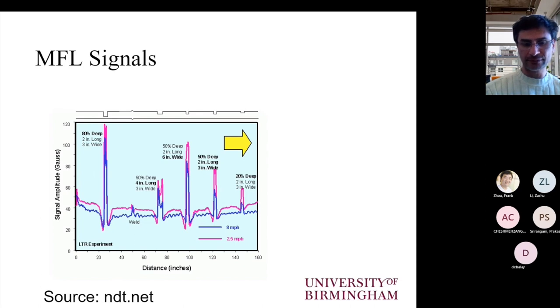So the purple trace is the inspection carried out at 2.5 miles per hour, and the blue trace is at 8 miles per hour. Here you can see that the response for the higher speed inspection is somewhat reduced, even though the defects are mostly detectable in both cases. But the amplitude of the response is lower in the second case, and this is because of the eddy current effects, which are caused by the fact that the probe is moving faster along the component that we are inspecting.